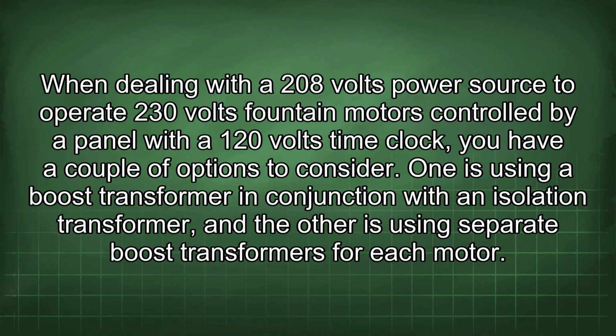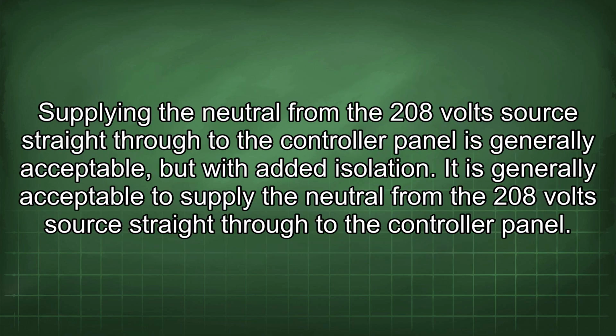When dealing with a 208 volts power source to operate 230 volts fountain motors controlled by a panel with a 120 volts time clock, you have a couple of options to consider. One is using a boost transformer in conjunction with an isolation transformer, and the other is using separate boost transformers for each motor. Supplying the neutral from the 208 volt source straight through to the controller panel is generally acceptable, but with added isolation.